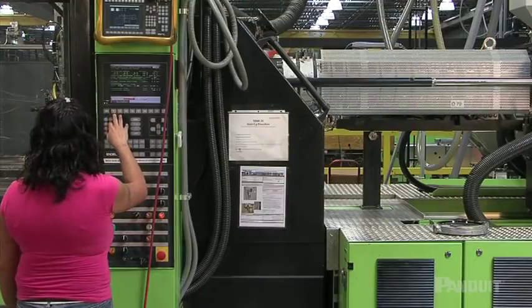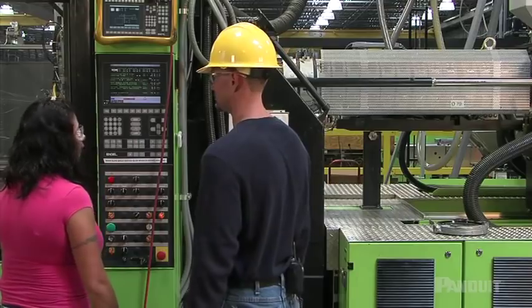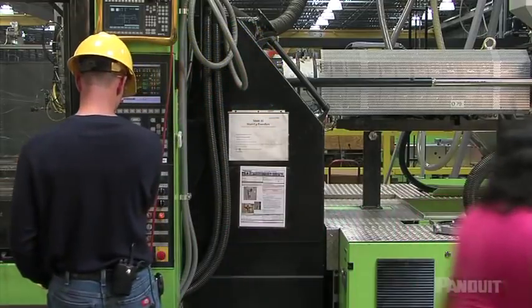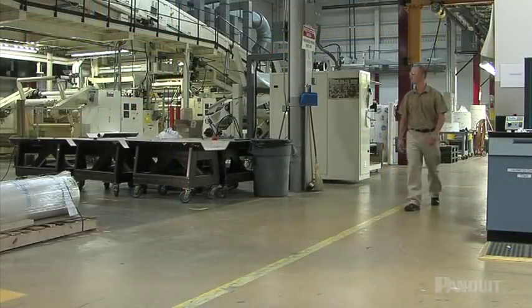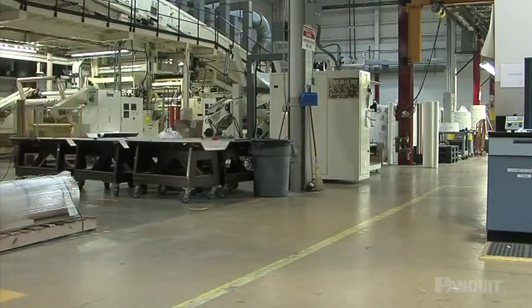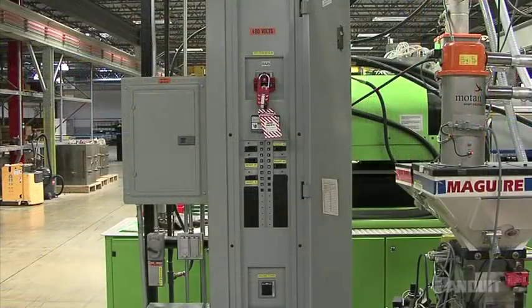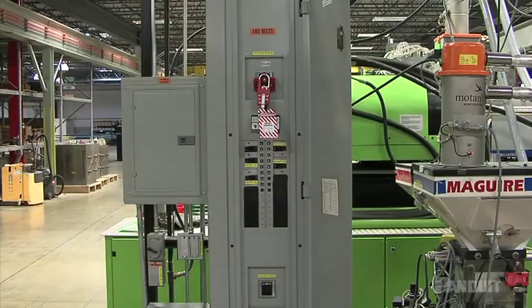Affected employees simply perform their duties in the area in which an energy control procedure is being implemented. Affected employees are not responsible for locking and tagging out, and they are not authorized to do so. Other employees include office or warehouse personnel who may work in an area where an energy control procedure is utilized. The responsibilities of affected and other employees are to recognize when energy control procedures are being implemented, understand their purpose, not attempt to start up equipment that has been locked or tagged out, and relay all such requests to the authorized employee on duty.